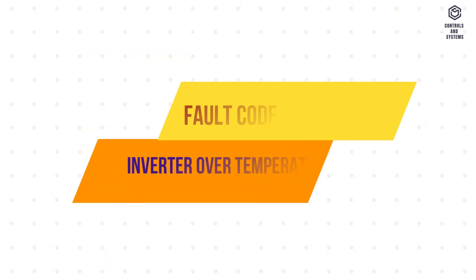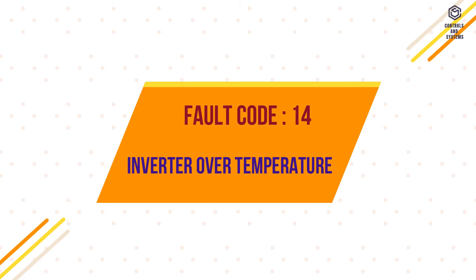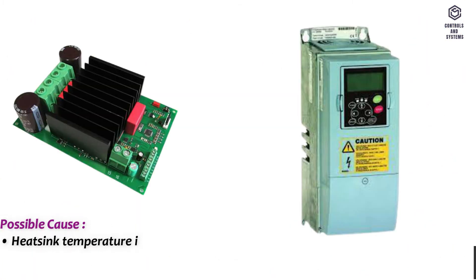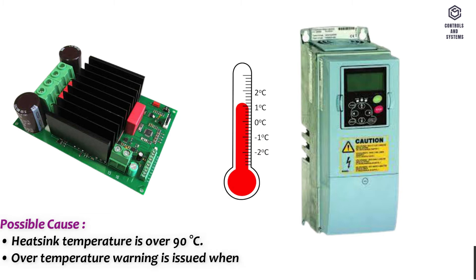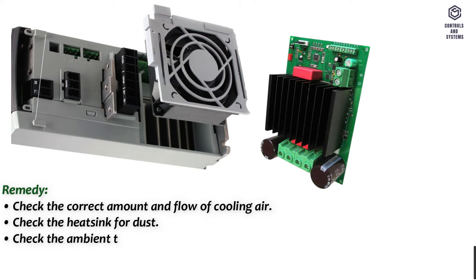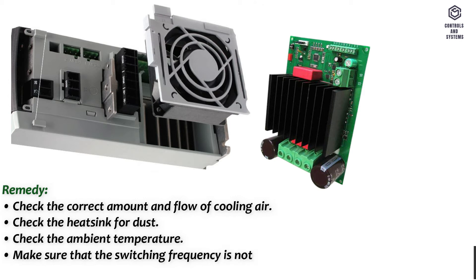Fault code 14 – Inverter over temperature. Possible cause: heat sink temperature is over 90 degrees Celsius. An over-temperature warning is issued when the heat sink temperature exceeds 85 degrees Celsius. Remedy: check the correct amount and flow of cooling air, check the heat sink for dust, check the ambient temperature, and make sure the switching frequency is not too high in relation to ambient temperature and motor load.